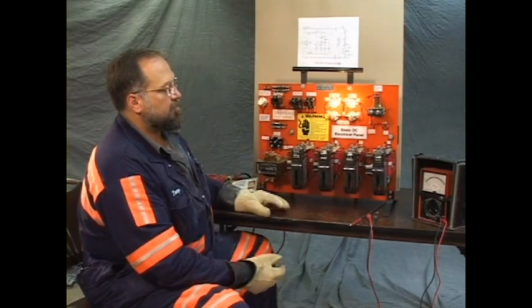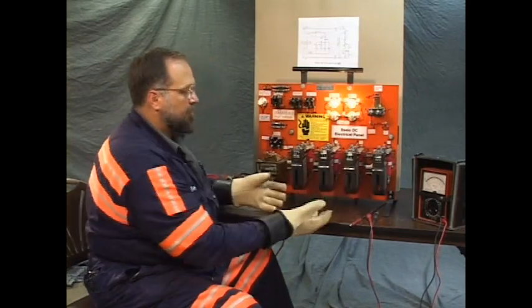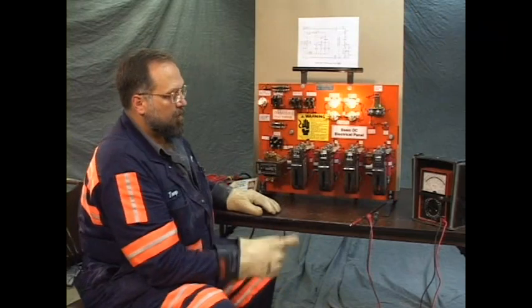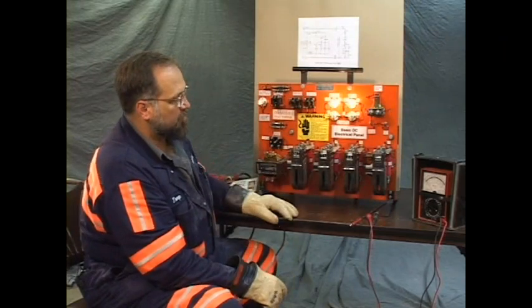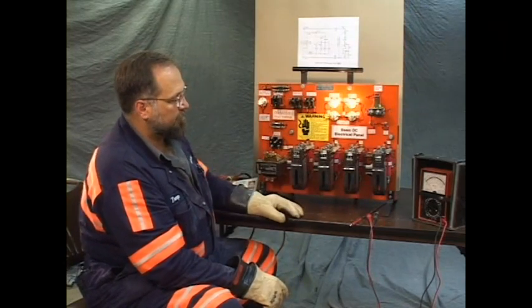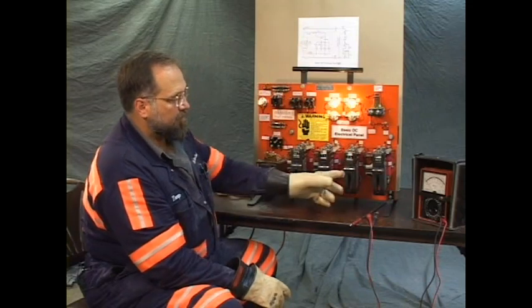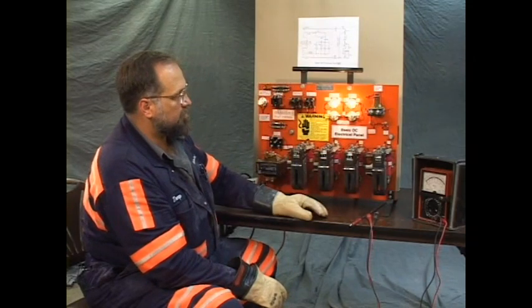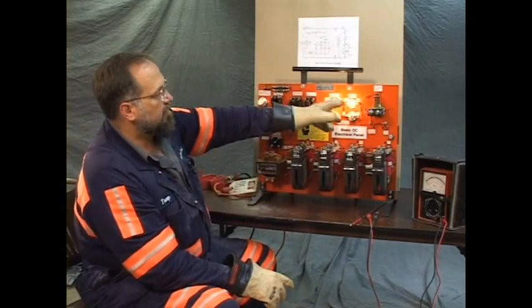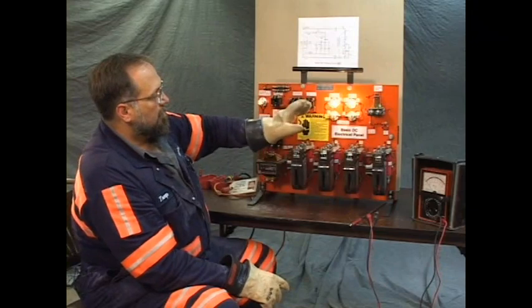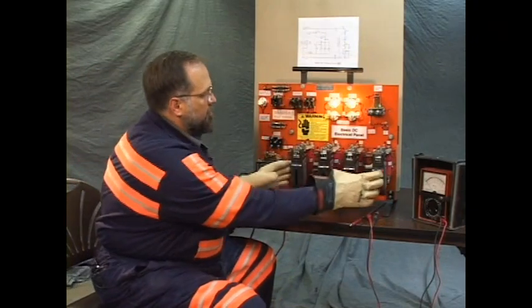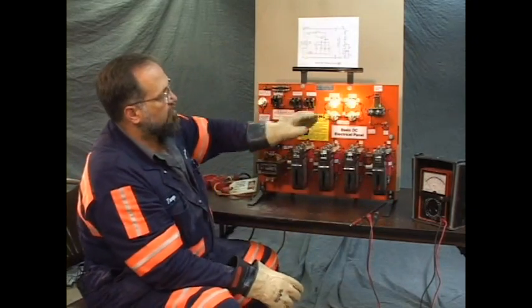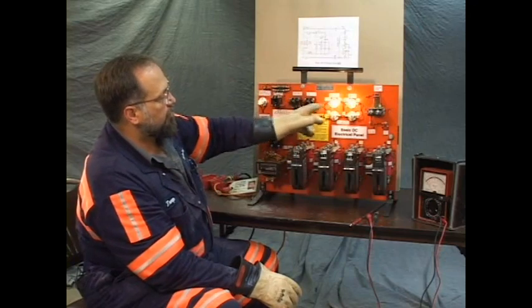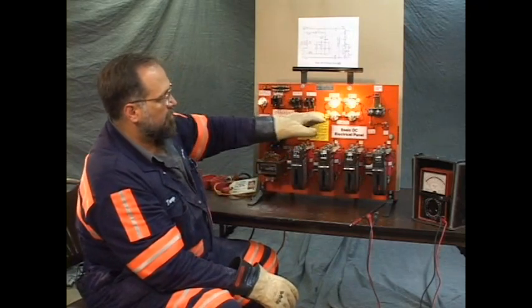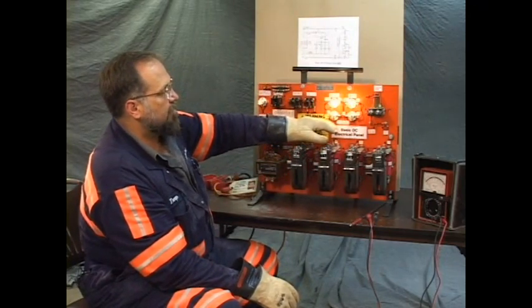2 of the contactors go in simultaneously. M1, M2 go up at the same time. After 1 second, 1A goes in. It closes. After 1 second, 2A goes in and closes. The effect of that on these lights, when you initially close these 2, all 4 lights are on. The shunt field light is bright. These 2 on the bottom are dim.